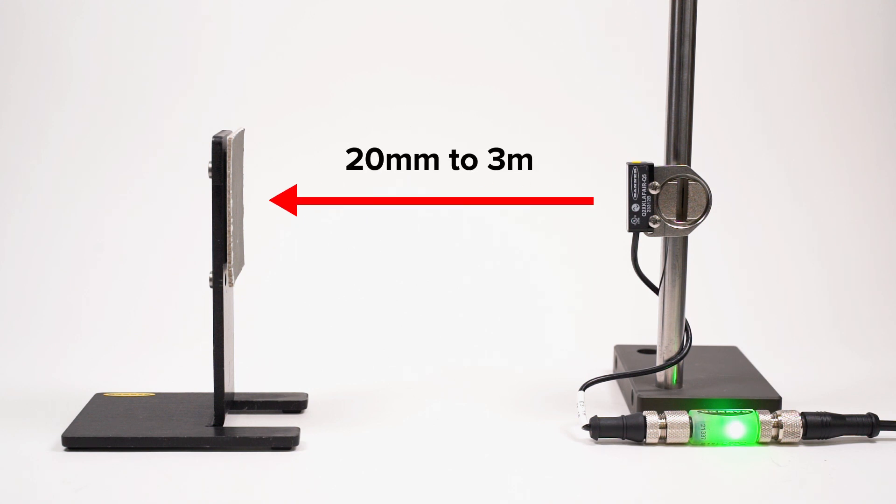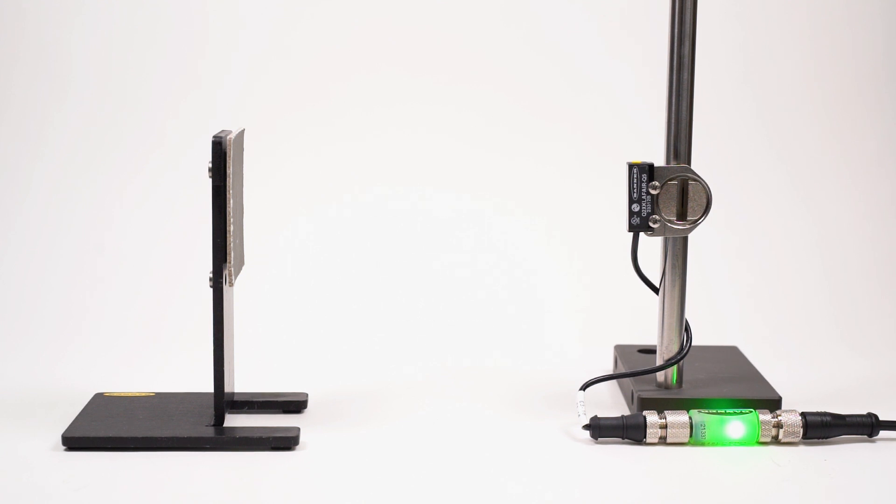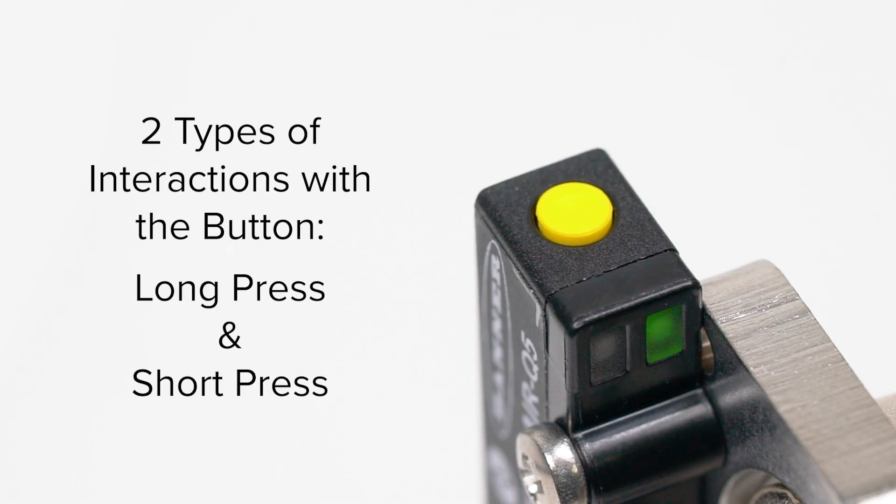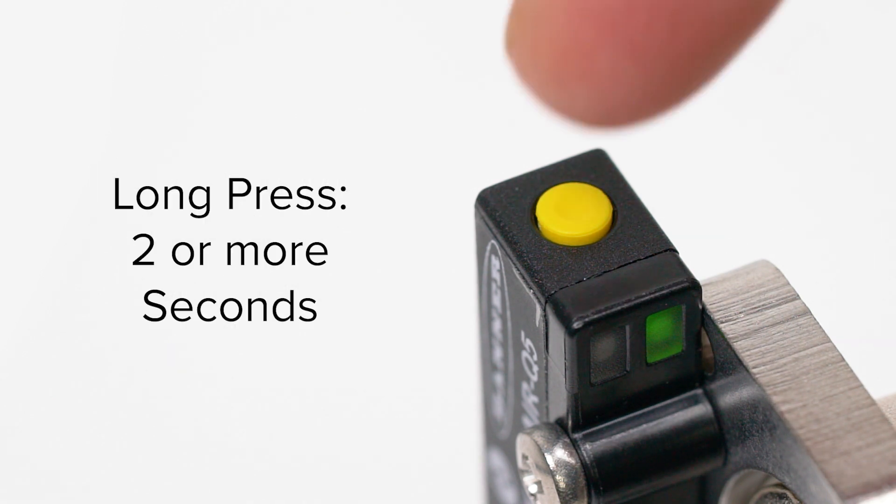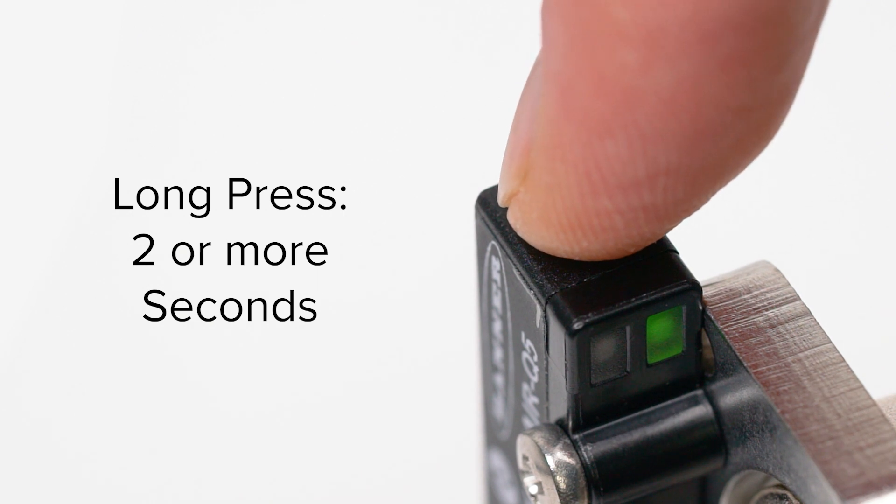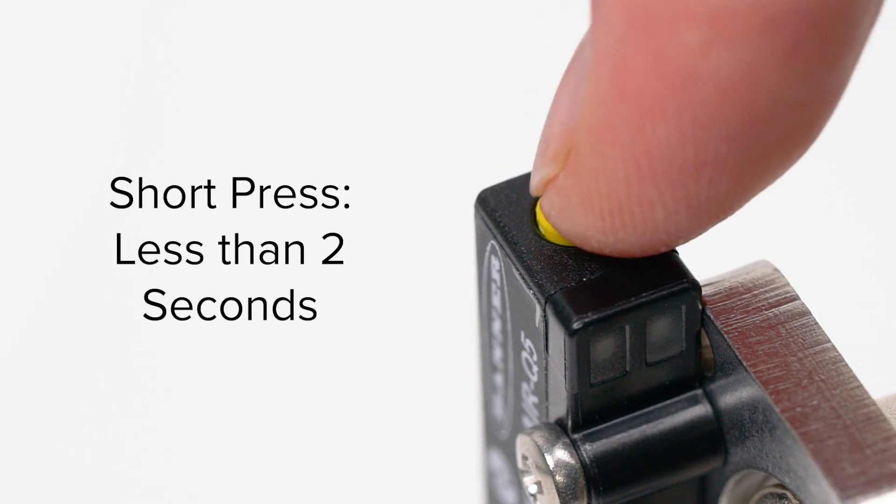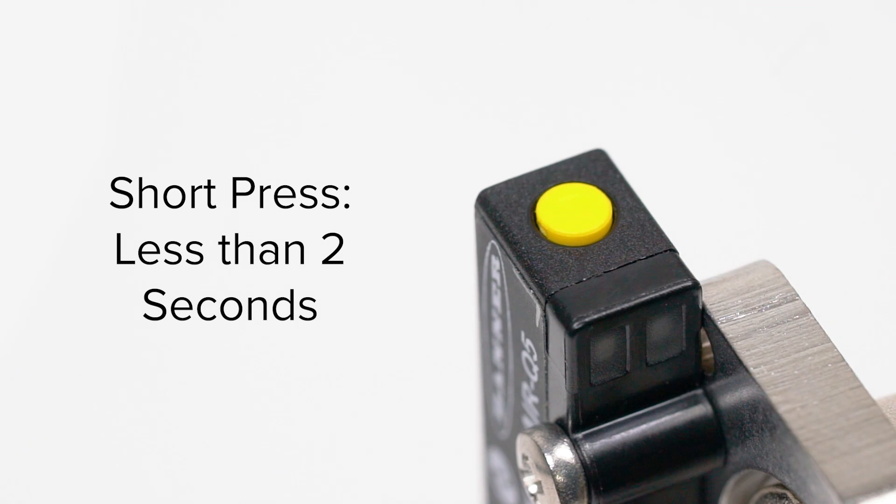It can be taught with the push button on top of the housing or using the remote input wire or IO link. There are two types of interactions with the button: a long press and a short press. A long press is when you press the button for two or more seconds. A short press is when you push the button for less than two seconds.